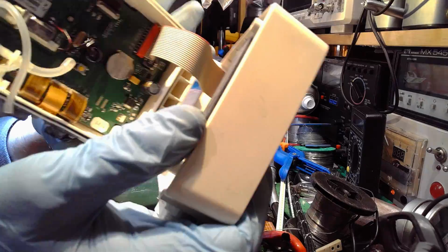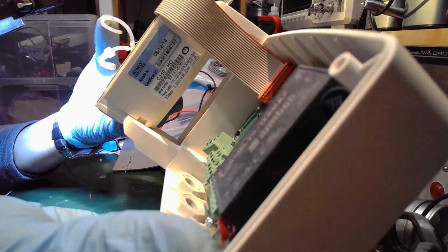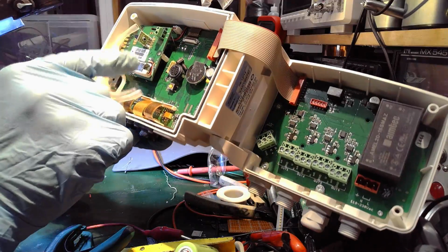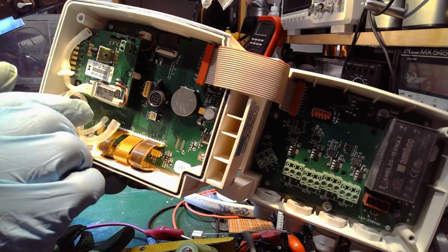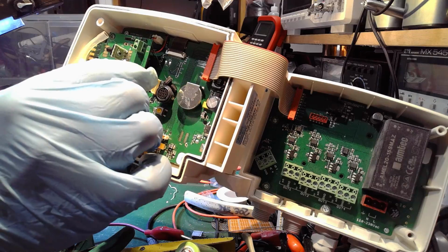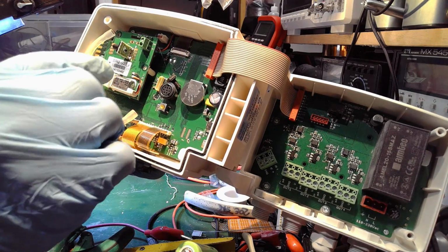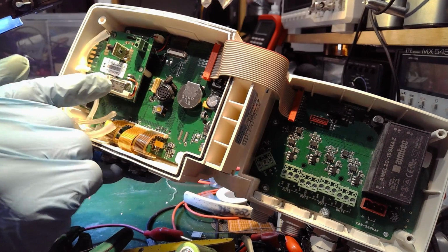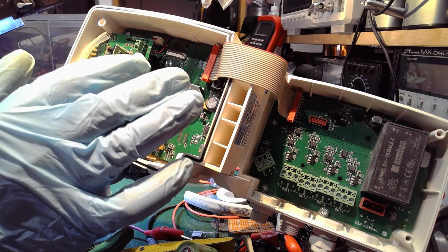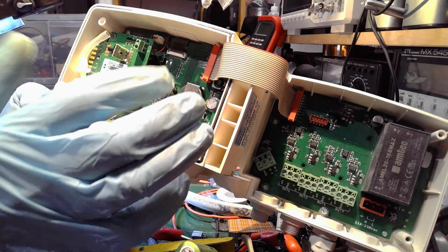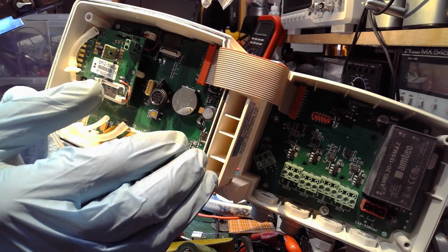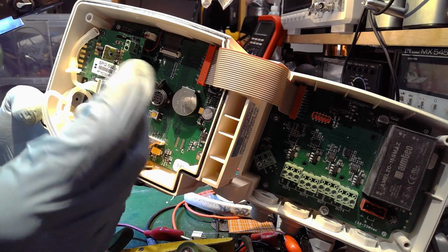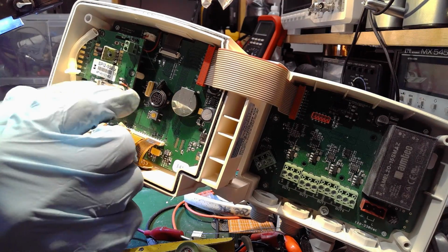You have a special component on inside, and you can see here, pretty dismounted, this little board, which is actually the board containing the sensor, and this is here just a valve helping the device to make a good calibration from time to time, so there's no drift of the zero of the device.